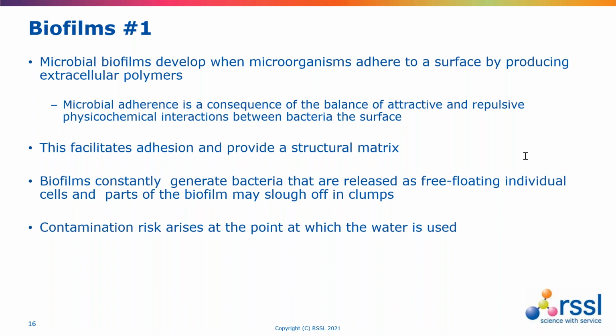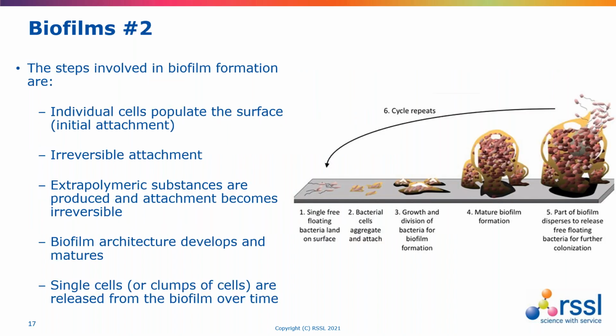And the primary weak point, as we'll look at in a little bit, is with poorly designed pipes, particularly where the water flow goes down. The main challenge presented to contaminated water systems is where the organisms are slowly released. So we get this pattern of free-floating cells that are released in clumps.